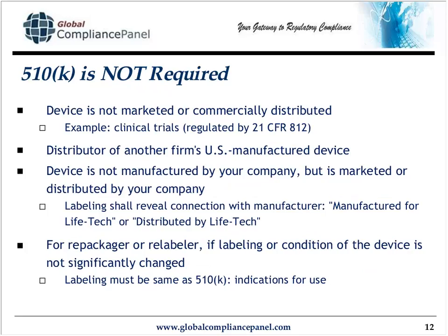If the device is not manufactured by your company, but is marketed or distributed by your company, in this case, the labeling has to reveal the connection with the manufacturer. If a company named LifeTech, for example, is the distributor, they may choose to indicate on their labeling manufactured for LifeTech or distributed by LifeTech, whichever one. Either of these clearly indicates the connection.